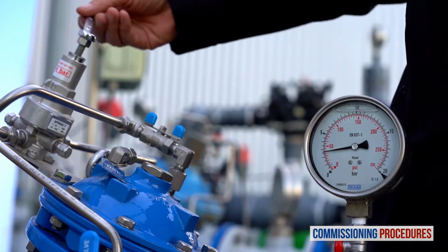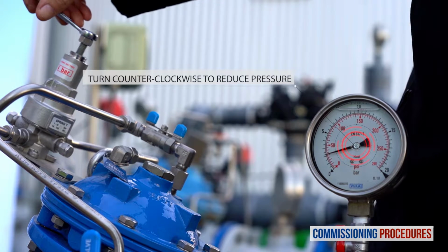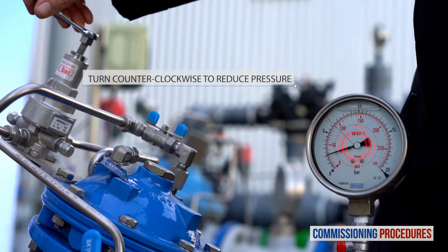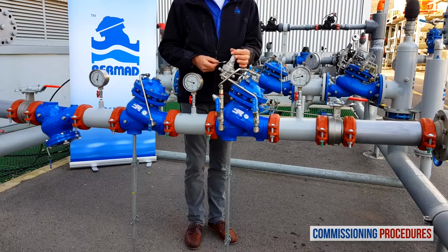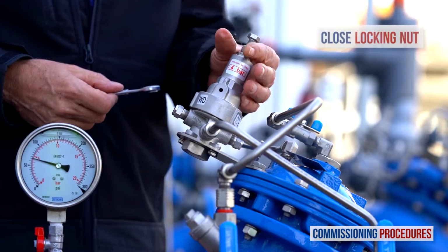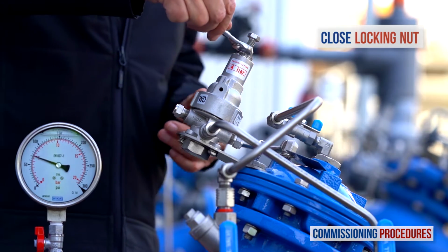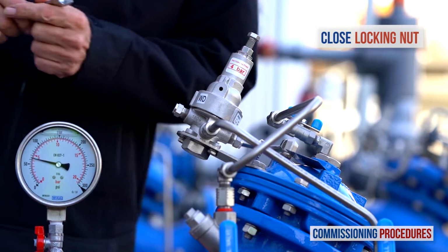To reduce downstream pressure, follow the same process, but in this case, turn the adjustment screw counterclockwise. Once you have reached the desired downstream pressure, close the pilot's adjustment screw locking nut and replace the protective cover.